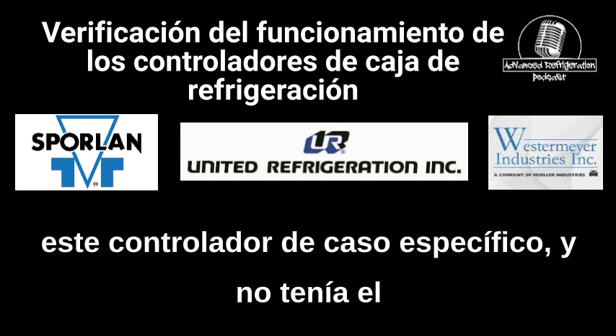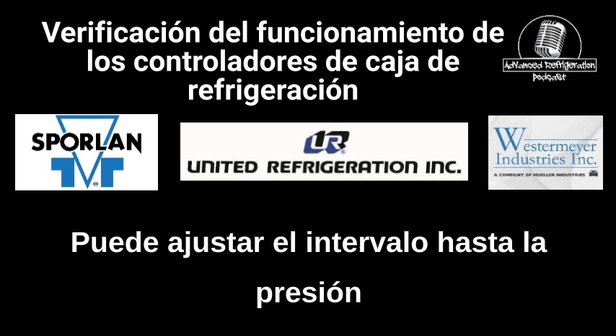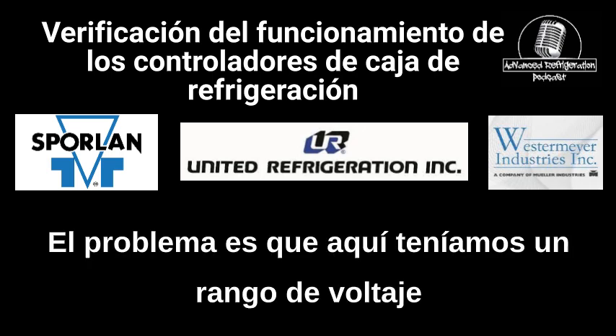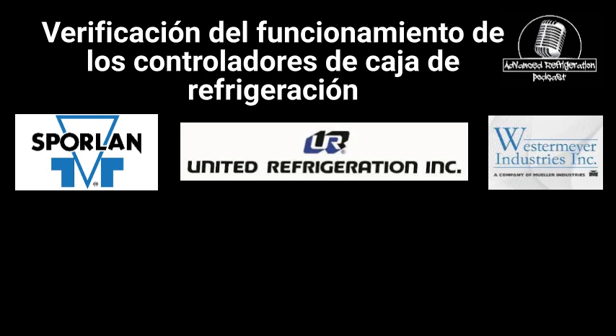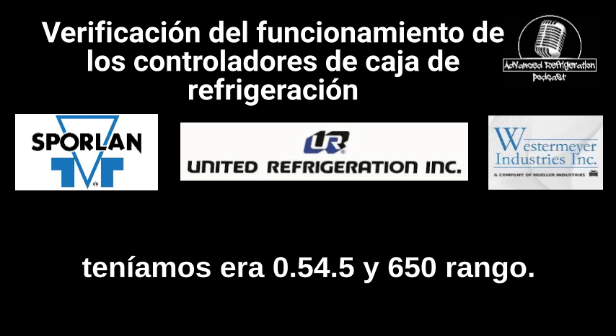we were looking at this specific case controller and it didn't have the option for the pressure transducer that was in there. You can adjust the span as far as the pressure rating, but you can't do anything with the voltage. So the problem here is we had a voltage range set for either 0 to 10, 0 to 5, or 4 to 20 milliamps. And the pressure transducer we had was 0.5 to 4.5 volts and 650 range.